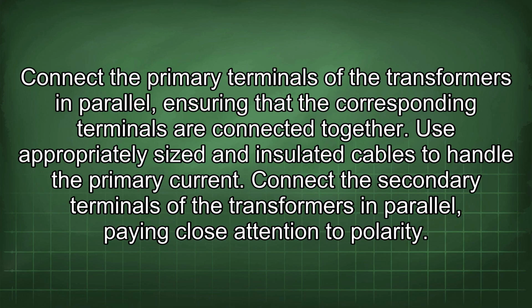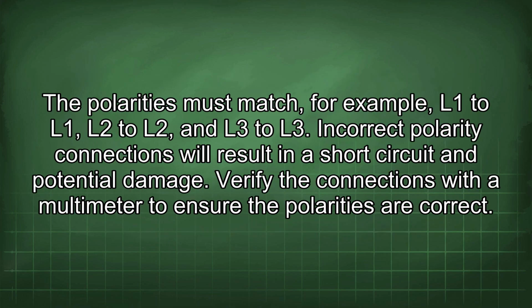Connect the secondary terminals of the transformers in parallel, paying close attention to polarity. The polarities must match, for example, L1 to L1, L2 to L2, and L3 to L3. Incorrect polarity connections will result in a short circuit and potential damage. Verify the connections with a multimeter to ensure the polarities are correct.